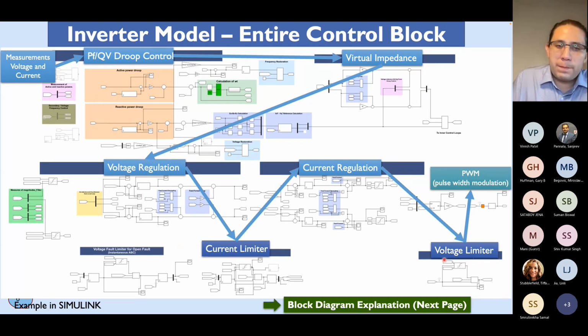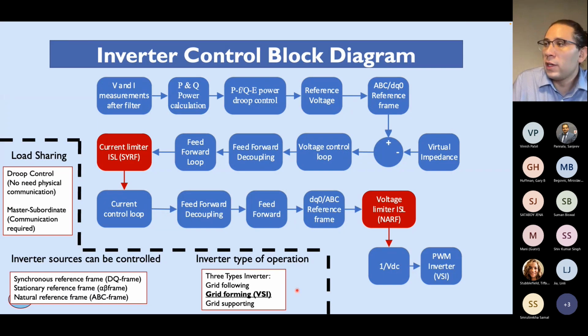So the following figure is showing the control of the inverter. I won't spend too much time here. I will explain later on in the following slides. But here I'm marking the most important sections because the slide is a bit heavy, so it would be very difficult to go through this one. Basically, here we are showing the control system shown in the previous slide, where we have the voltage and current measurements that go to the P and Q power calculation used for the droop control. From here we generate the reference voltage, and with the virtual impedance we can calculate the voltage loop control, which is in level 1, as I showed in the previous slide.